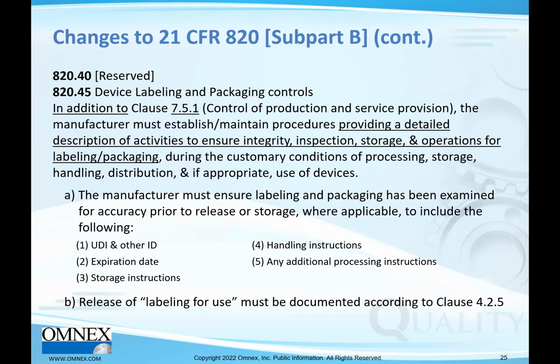the manufacturer must establish and maintain procedures providing a detailed description of activities to ensure integrity, inspection, storage, and operations for label and packaging. The manufacturer must ensure that the labeling and packaging has been examined or inspected for accuracy prior to release or storage, and needs to include, where applicable, and it is always considered applicable unless you have it documented otherwise in writing, the UDI or other identification, expiration dates, storage instructions, handling instructions, and additional processing instructions at a minimum.